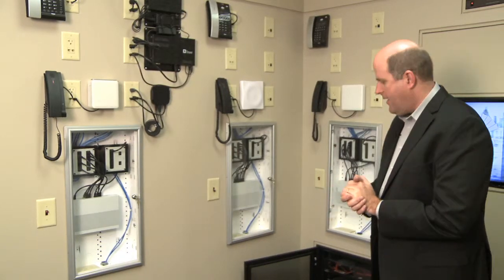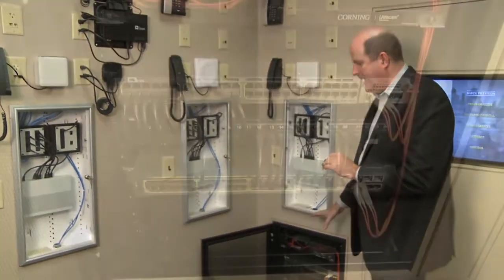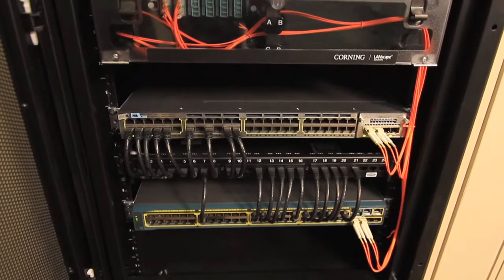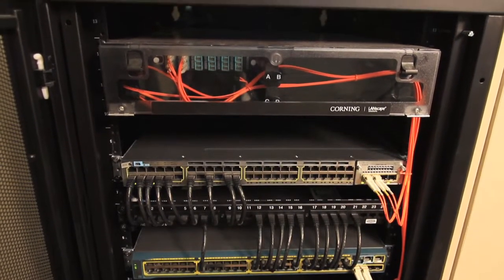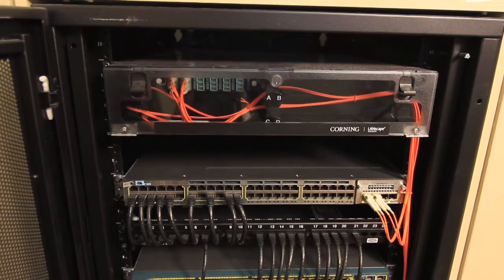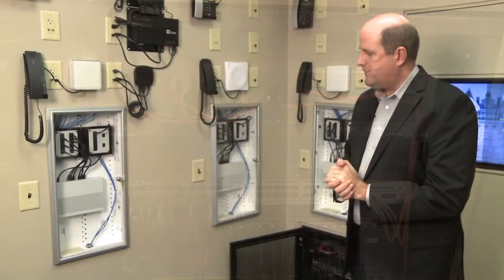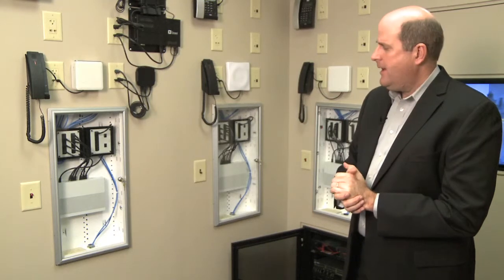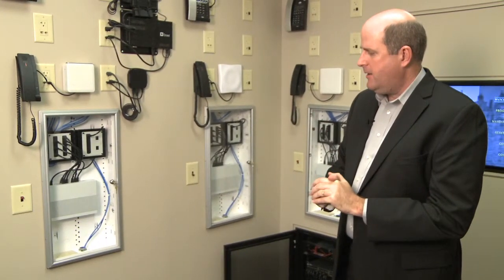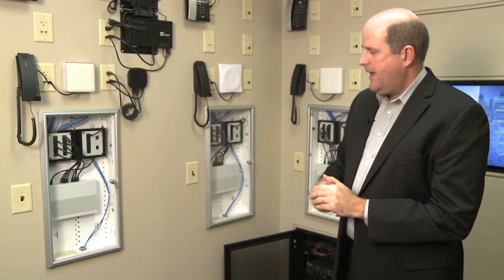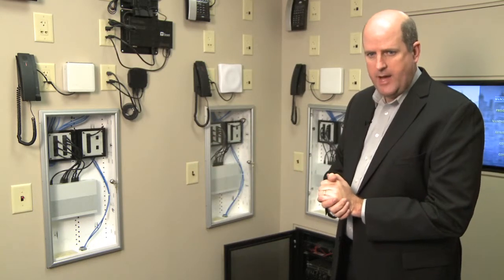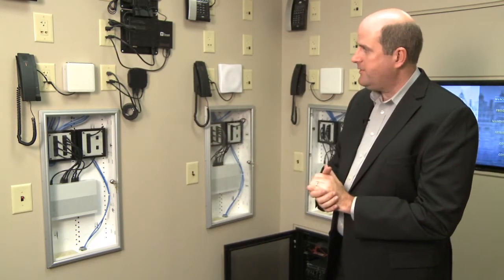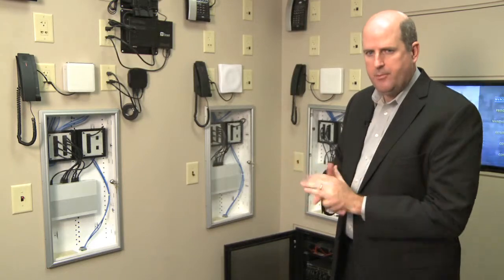So during a power outage, as long as the IDF has backup generator circuit and UPS circuit, the guest room will stay up and running and operate. Coincidentally, two weeks after we installed it, we actually had an extended power outage over one weekend in Boston. The Back Bay had a single day power outage, and the Cisco switches actually operated as intended, and all the wireless access points and phones continued to operate during that outage.